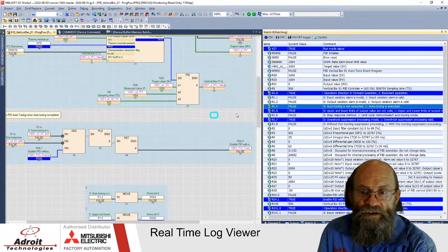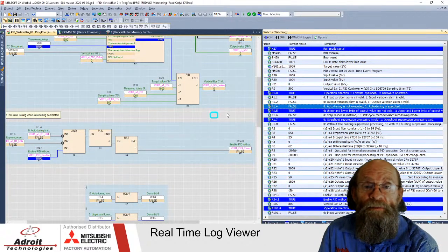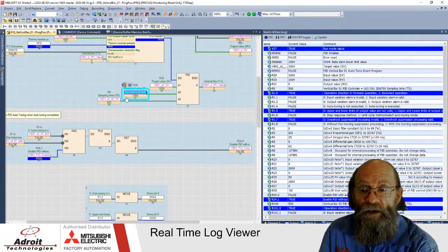As my temperature changes, my output, for instance, I'm driving a solid state relay, and that will control the temperature on my element. And then obviously the temperature sensor that I use on the element will feed the information back into S2 of the PID controller.